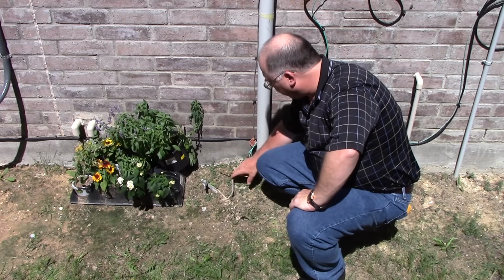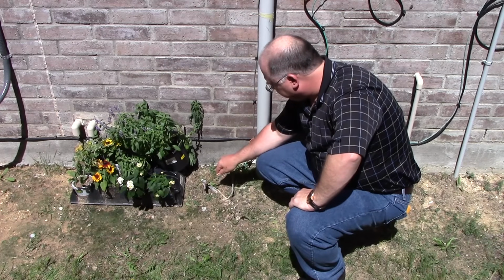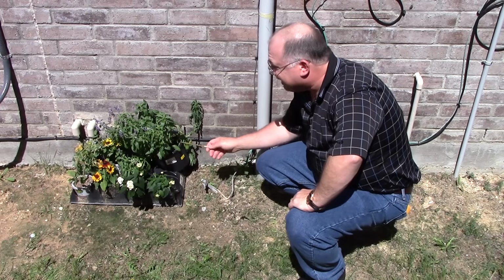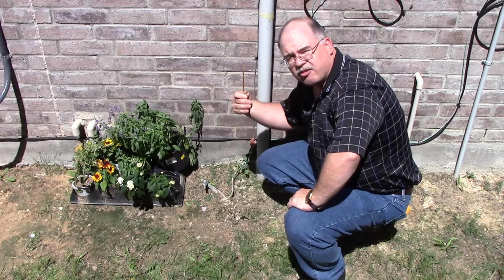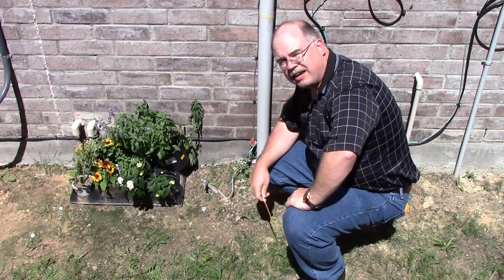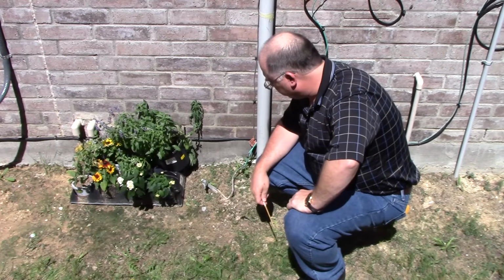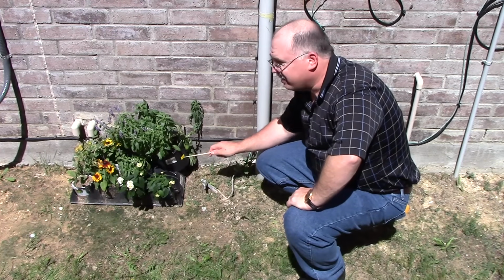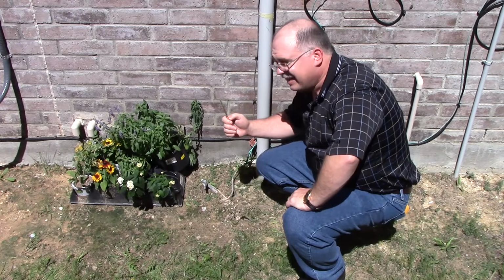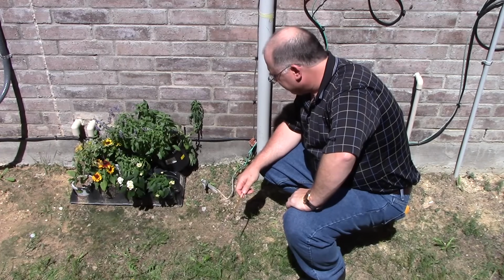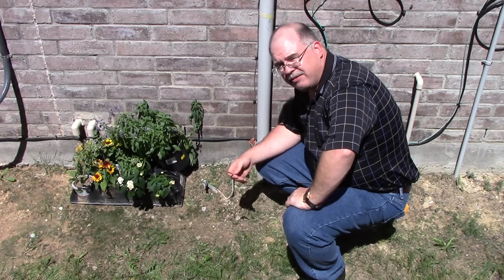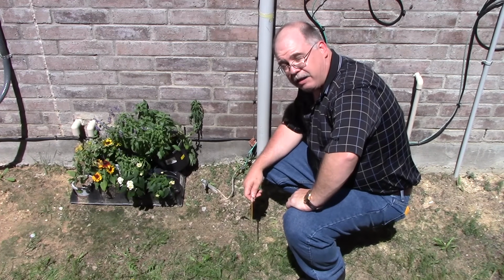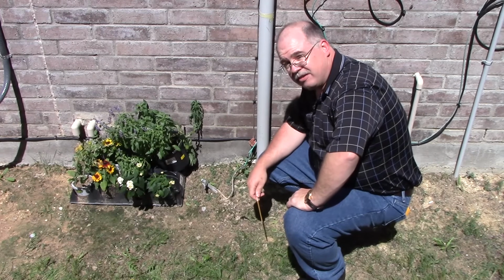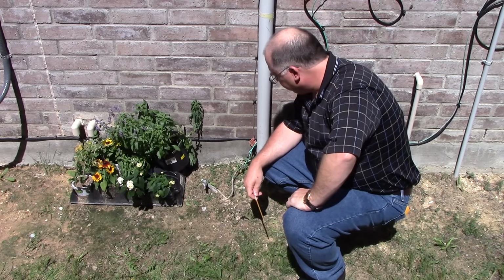All right, so this is installed okay. Don't have any problems with it. It is a proper acorn clamp. Again, since there's already a concrete-encased electrode here, I'm not going to recommend a second one. This is good enough if they want to do it this way. Again, if this was the only one, then I would have them have two, at least 6 feet apart. Okay. Conventional theory among some people believes they should be 8 feet apart, the same length as the rod, but the code says it only has to be 6 feet apart. All right. So that looks good.